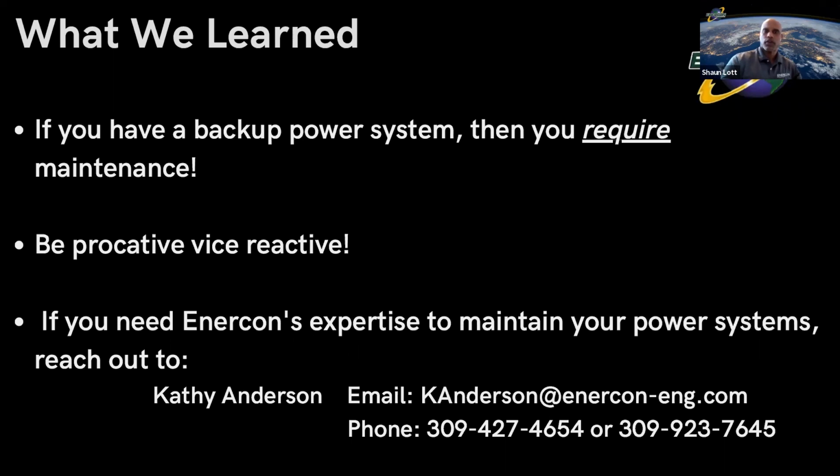Or does it vary? Well, that depends on your generator manufacturer, because that's driven by your generator. Most generator manufacturers recommend at least 30% load for 30 minutes. So 30% for 30 minutes. Okay. And normally, that's what I've heard from most of the generator technicians that I work with, is that's the bare minimum that you should do. But really, load it with as much load as you can give it. If you can give it 80% load for 30 minutes, great. It'll love it. Okay. And a follow-on question to that is, what materials are required during the monthly maintenance?